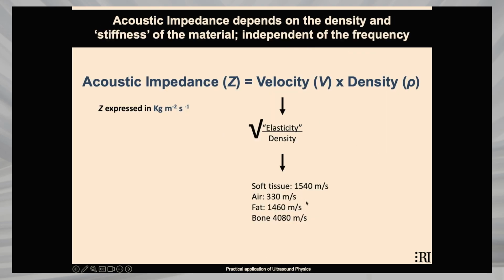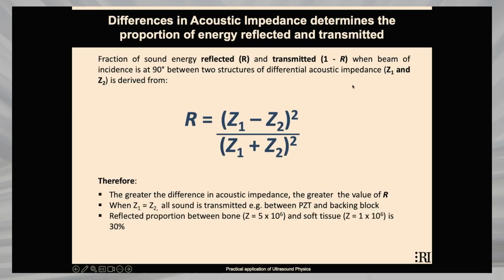Now, acoustic impedance is a really important principle, because it is the difference between the acoustic impedance of different materials that determines how much sound wave makes it back to the probe. So acoustic impedance is based on the velocity of sound waves through various materials, and these are fixed, that you can see through soft tissue, air, fat, and bone, and then the density of that material. And what determines what goes through and what gets reflected back is the differences in the acoustic impedance. Therefore, the greater the difference in acoustic impedance, the greater the value of R. Okay? So that's the greater the value of R. It's dependent on how much difference there is.